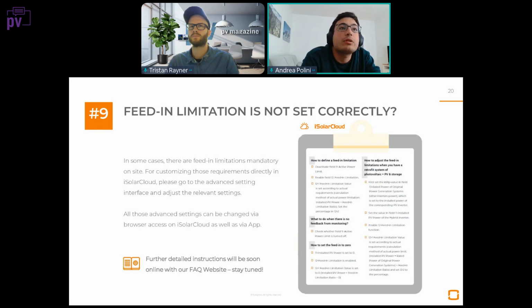And so first, you need to go to the settings menu in your plant. If you didn't set it during commissioning, in the settings menus of your plant installation in iSolarCloud, you will need to select the hybrid inverter or the PV inverter that you want to change the settings for. Then you need to go to advanced settings and power settings. In this menu, you need to set the information that is shown here on the slide, and you can find a more detailed version also in the guide, where you need to set the specific feed-in limitation settings.